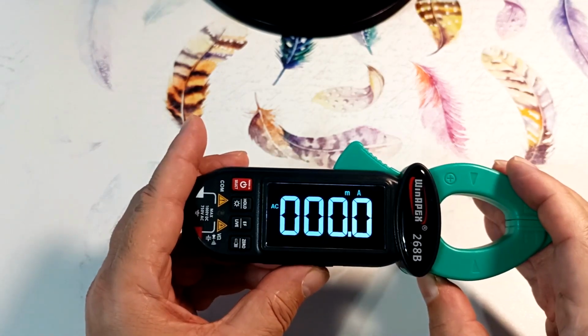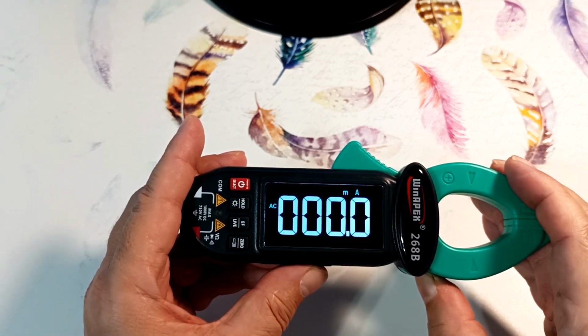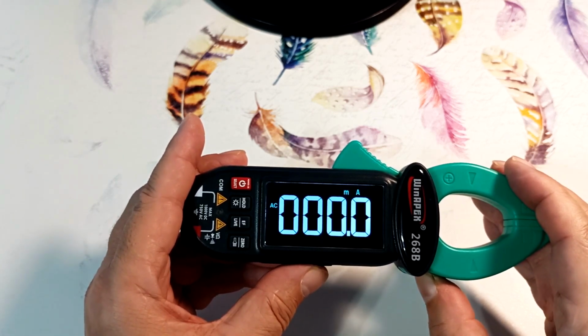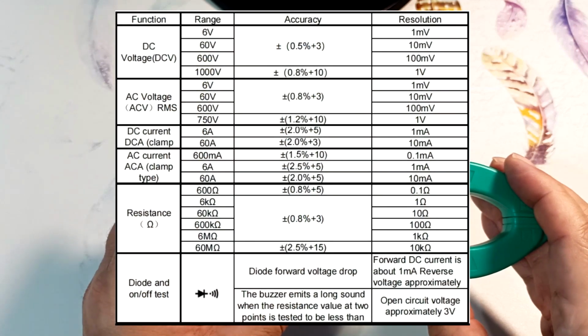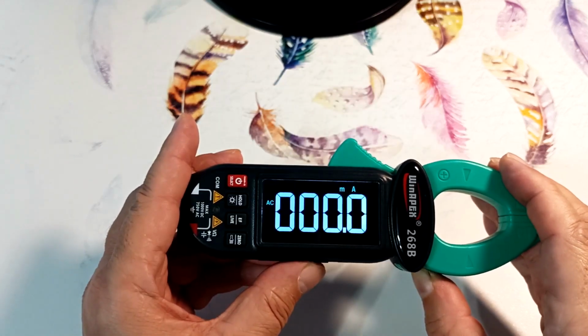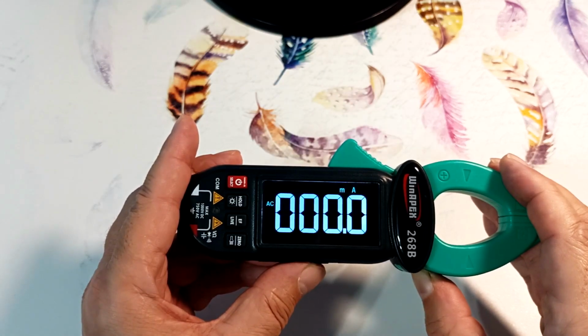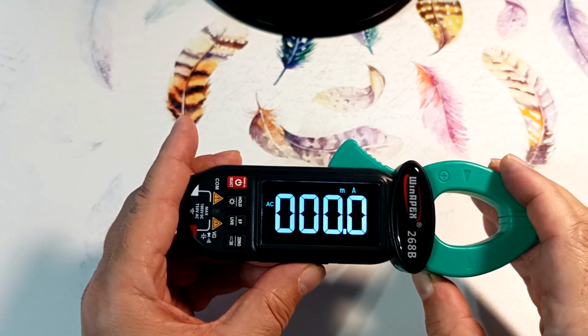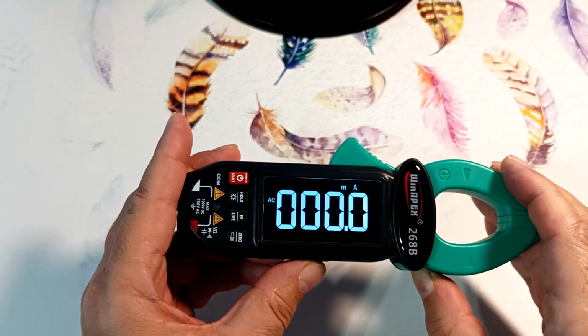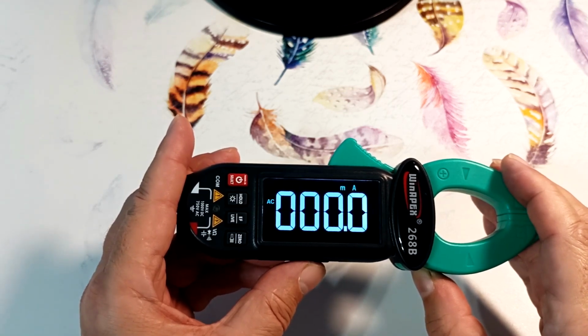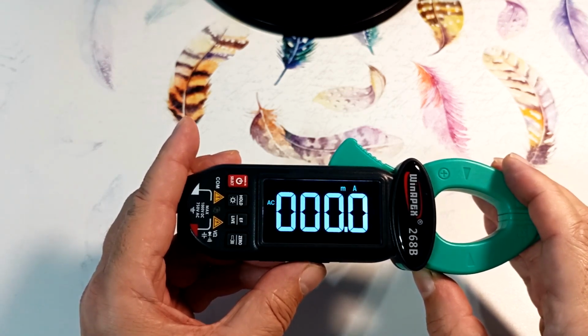By default, it includes the most sensitive AC current measurement range. In this range, it measures current from 2 milliamp in 0.1 milliamp steps. If the current is greater, then the device selects the measurement range itself. It measures the RMS value of alternating current up to 60 amp. In this range, the device can be used to measure small leakage currents.